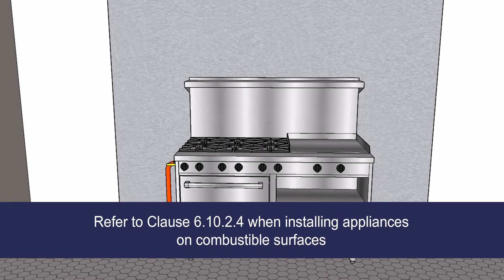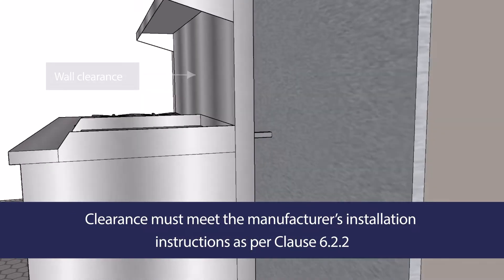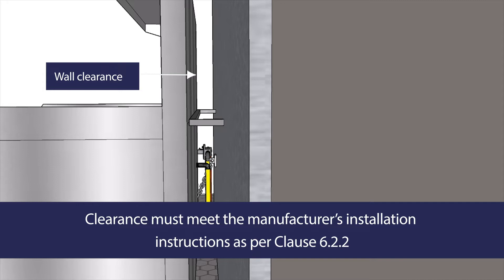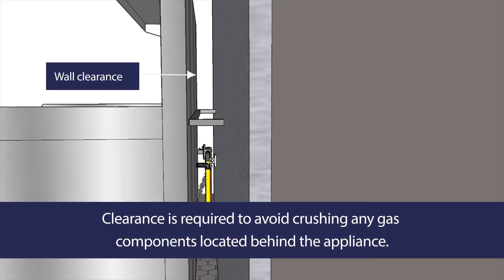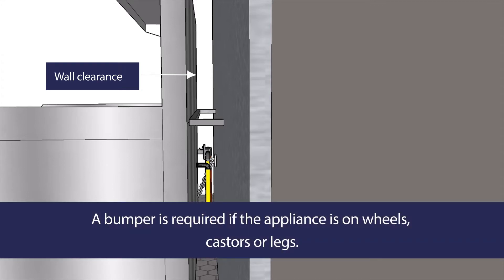Other aspects of the installation you must consider. The clearance between the gas appliances and the wall behind them is important for two main reasons. First, if the installation is against an unprotected combustible wall, the clearance must meet the manufacturer's installation instructions as per Clause 6.2.2. Secondly, clearance is required to avoid crushing any gas components located behind the appliance. A bumper the same size or greater than the required clearance must be installed to maintain the clearance at all times.